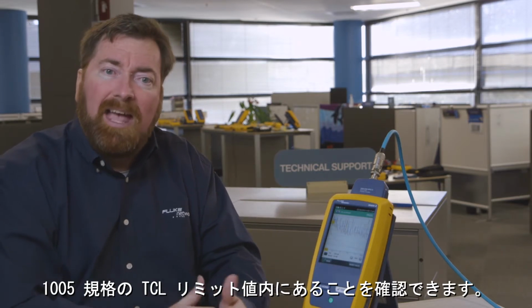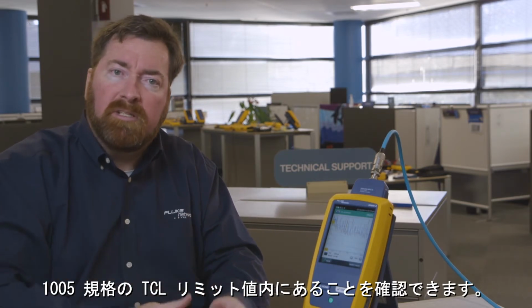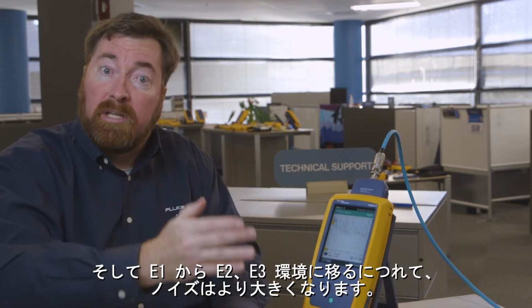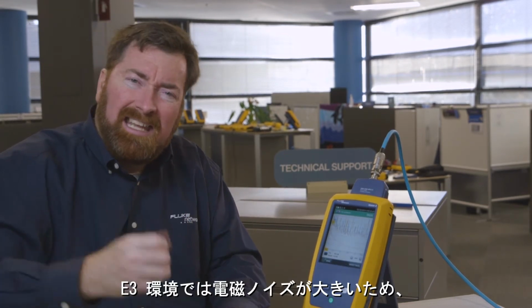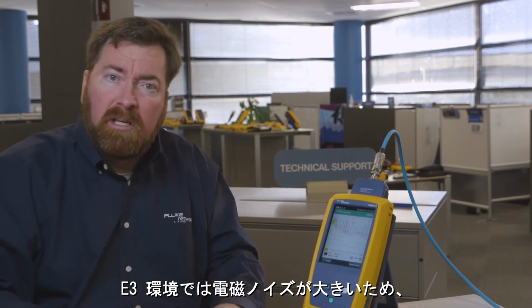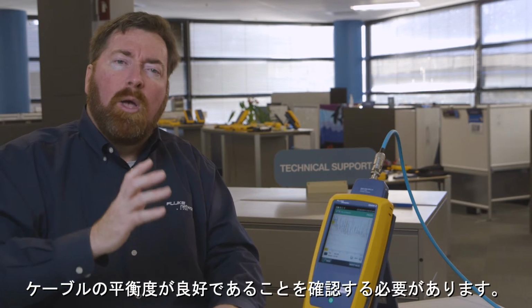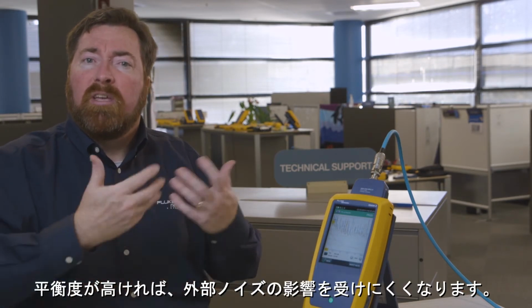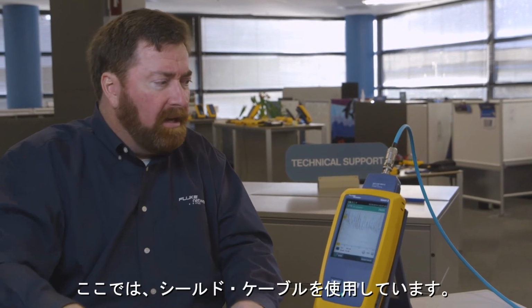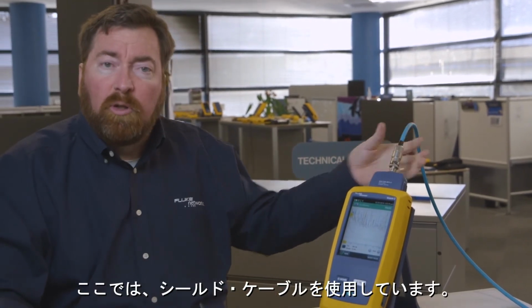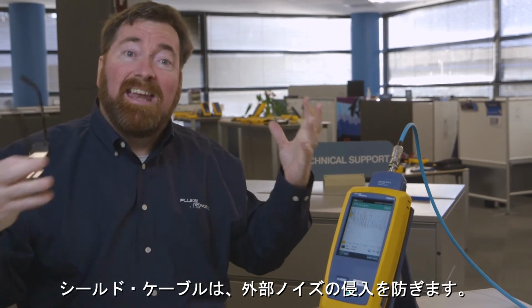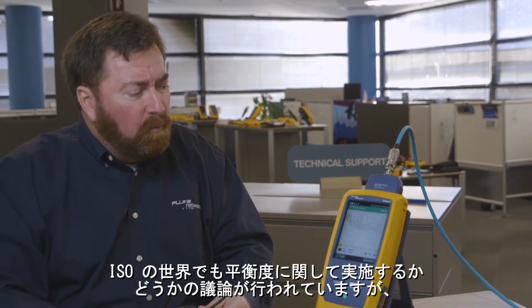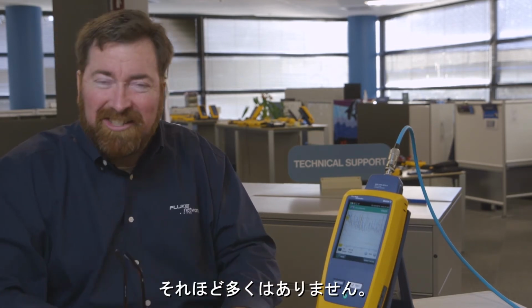The limits for the TCL test are in the 1005, and as we get to noisier and noisier environments, as we move from an E1 to an E2 or an E3 environment, an E3 environment that is more electronically noisy, we want to make sure that the cable has better balance. That means that it's more immune to external noise. Now, we are using a shielded cable, so the shielded cable should eliminate any of that external noise from getting in. And we'll find in the ISO world an open discussion about whether or not, well, it's not much of a discussion, in the ISO world, if you have a shield, you're not required to run these TCL tests.